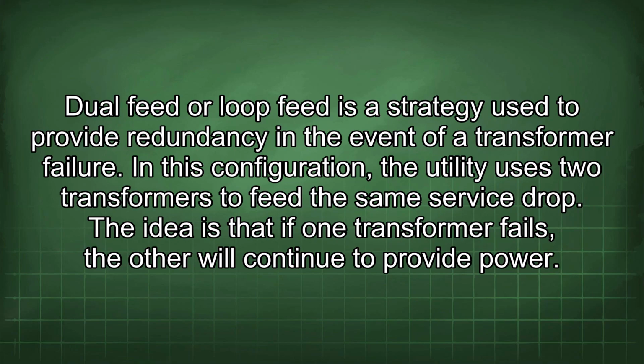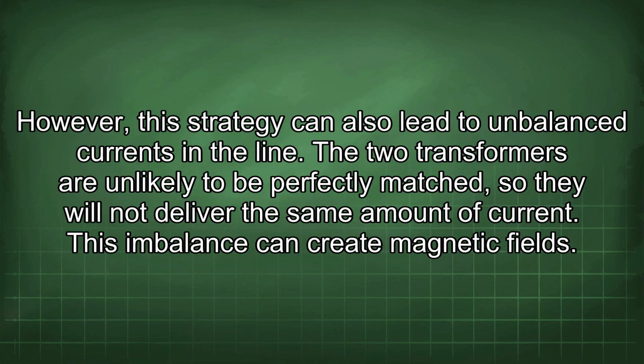Dual feed or loop feed is a strategy used to provide redundancy in the event of a transformer failure. In this configuration, the utility uses two transformers to feed the same service drop. The idea is that if one transformer fails, the other will continue to provide power. However, this strategy can also lead to unbalanced currents in the line.